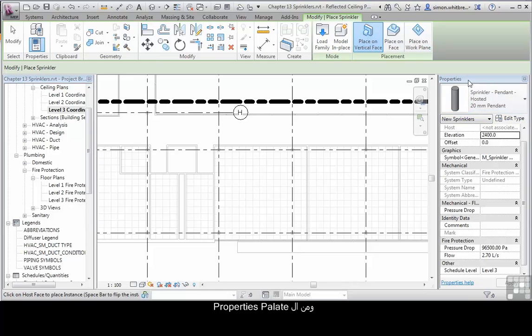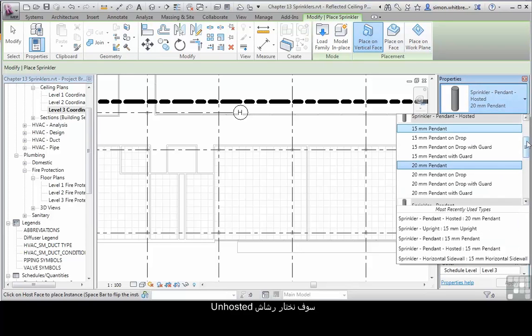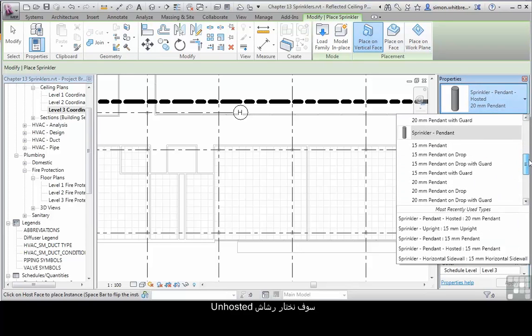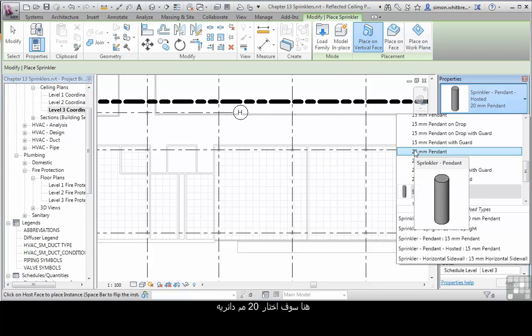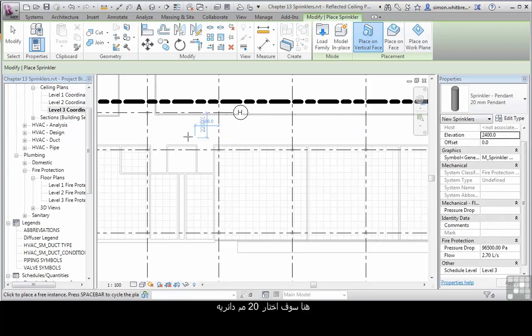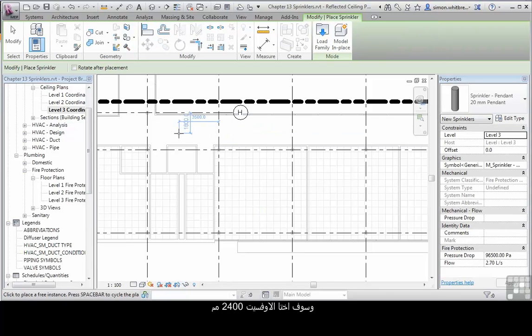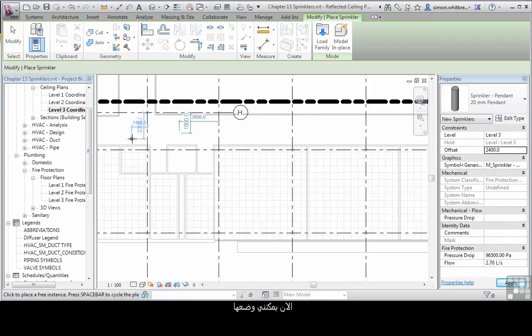From the Properties palette we're going to select a sprinkler head, a non-hosted one. Here I'm going to select a 20mm pendant. We'll choose its offset from the working level as 2400 and I can place a sprinkler.